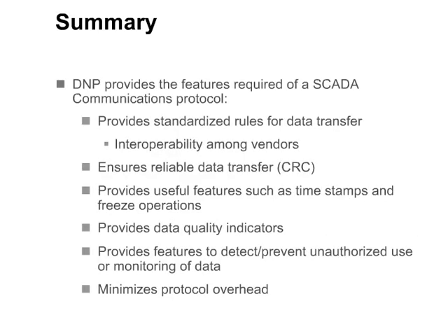DNP3 provides the features required of a SCADA communications protocol. It provides standardized rules for data transfer and promotes interoperability among vendors. It ensures reliable data transfer using CRCs. It provides useful features such as timestamps and freeze operations, provides data quality indicators, and provides features to detect or prevent unauthorized use or monitoring of data. It also minimizes protocol overhead.